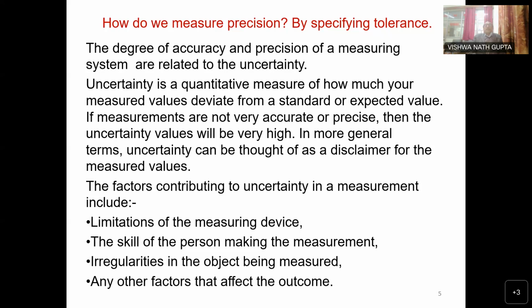The skill of the person making the measurement is also important. For example, earlier we used to have meter voltmeters with a glass mirror in the backdrop, and that caused what was called parallax error. The person had to see that the shadow of the needle was in line with the needle itself before taking the measurement; he had to be exactly in the 90-degree vertical position to read the value correctly.